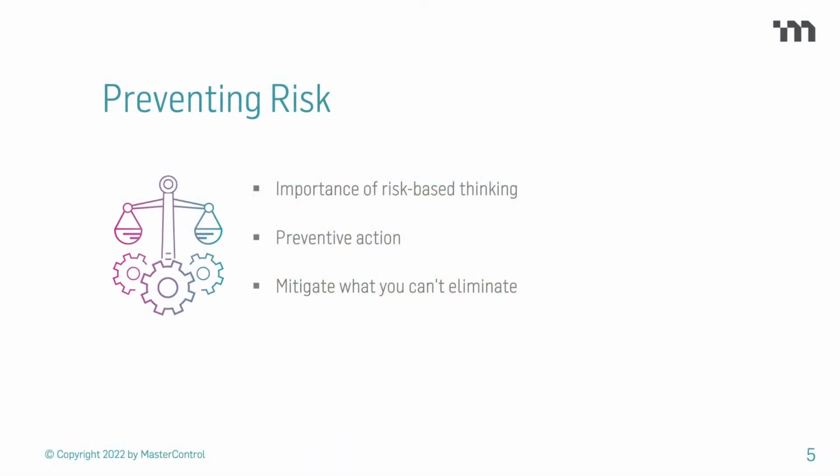Last, information for safety. In this, proper training is important, as is making apparent, clear, and human-readable warning and caution information. For a test, a machine, a process, anything that will require an operator, this helps them feel confident in the process and be safe. Instructions for use is included in this for the end user. These three principles and much more from ISO 14971 documentation help establish standards that you should create in your risk-based thinking.